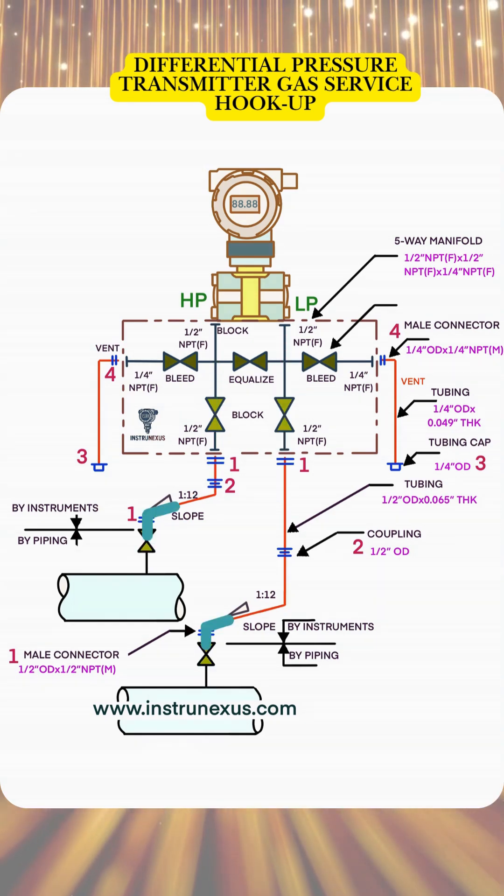During maintenance, simply close both block valves, open the equalizing valve, and bleed pressure safely through the vent.